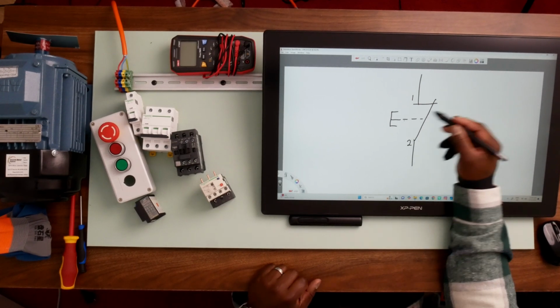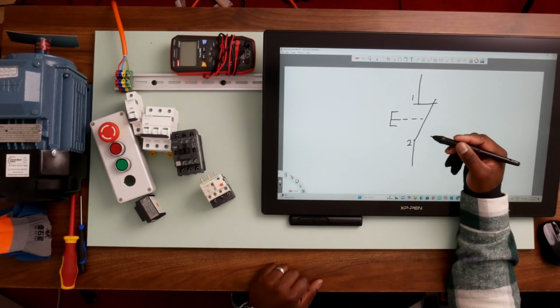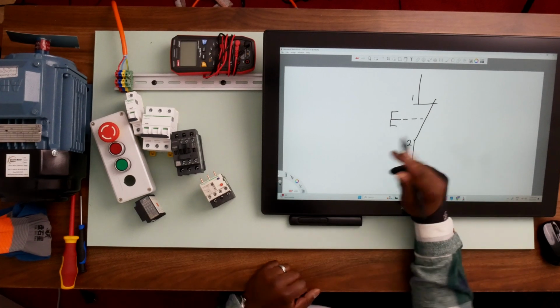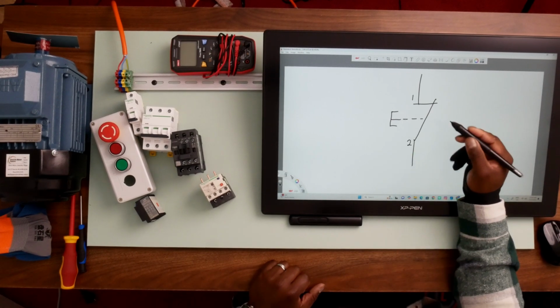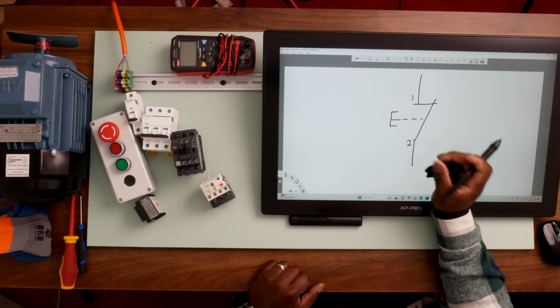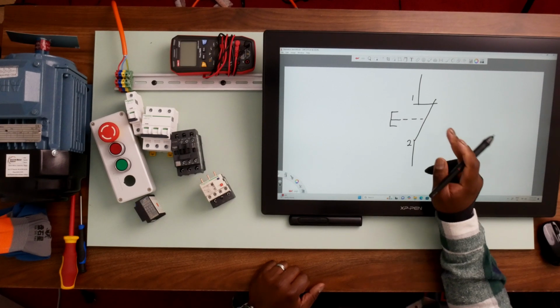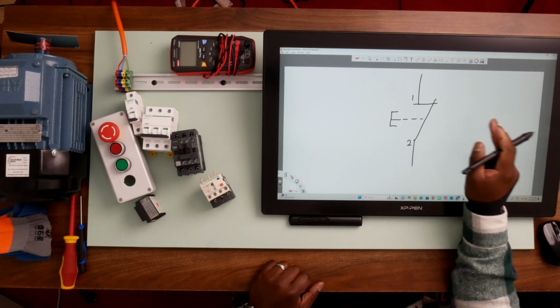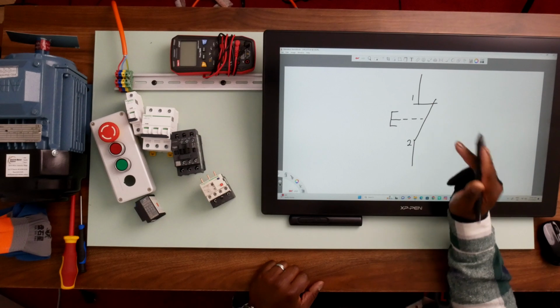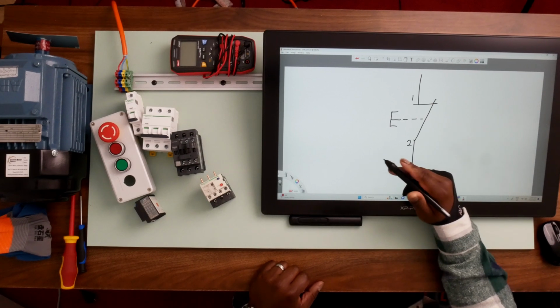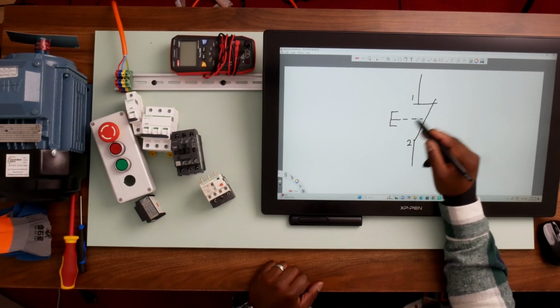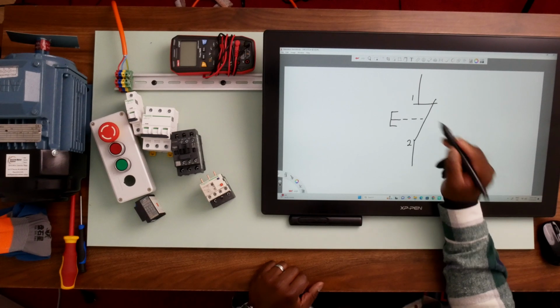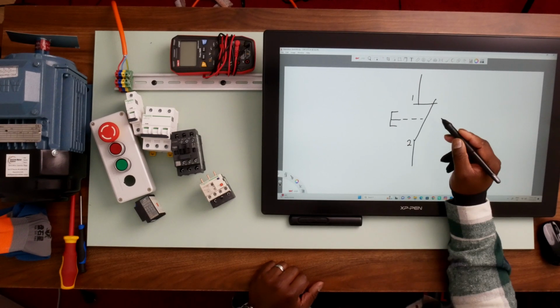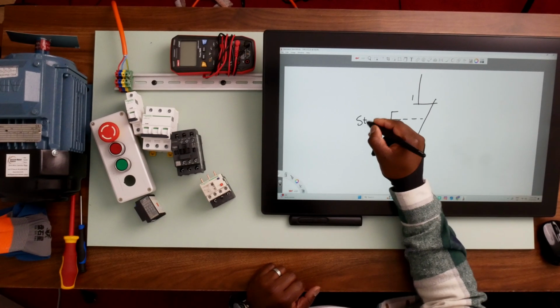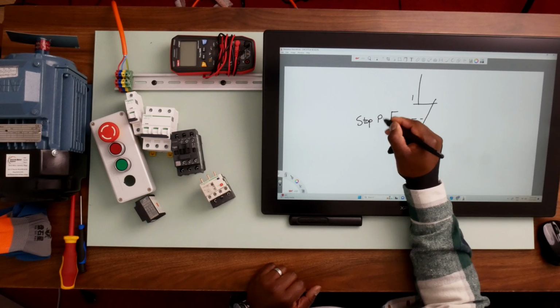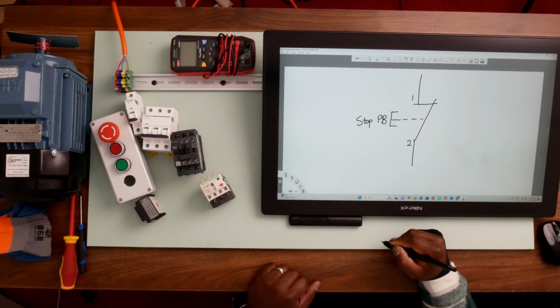Now, when you draw it like this, it tells us that it's a momentary contact. It doesn't latch. Which means that for a stop push button, it only remains in the open position as long as you keep your finger pressed on that button. But as soon as you release your finger from the push button, this contact is going to go back to its default state, which is the closed position. So this one is your stop push button.